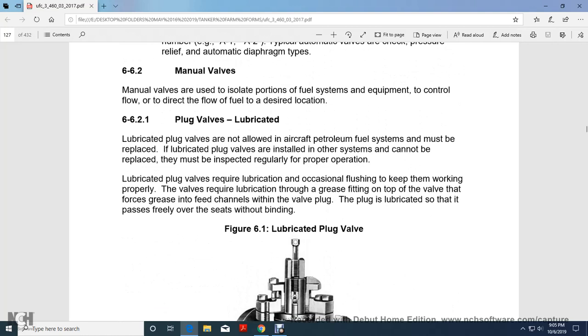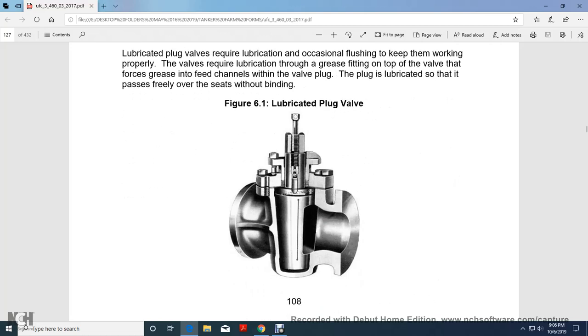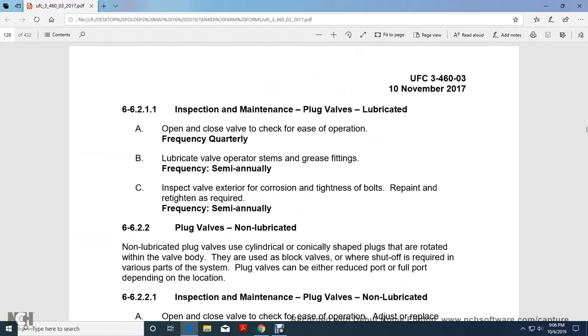6.6.2.1, plug valve. Lubricated plug valves are not allowed in aircraft petroleum fuel systems and must be replaced. Those installed with other systems that cannot be replaced must be inspected for proper operation. Lubricated plug valves require lubrication, occasional flushing to keep the working properties of the valve. They require lubricating with grease and a fitting at the top of the valve, with force, so the grease fits into the feed channel of the valve plug. The plug is lubricated so that it passes freely over the seats without binding. The lubricated plug valve is shown here.